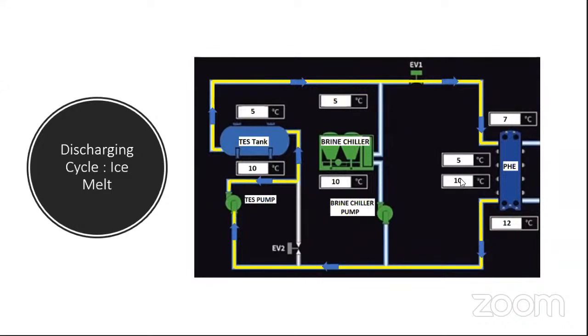Let us start from here. At 10 degrees centigrade, the brine solution is traveling here, and it is being drawn to the thermal storage tank. Across the thermal storage tank, the brine cools down to 5 degrees centigrade. And at 5 degrees centigrade, it comes to the PHE. Now, at 5 degrees centigrade it enters, and at 10 degrees centigrade it comes out. And here the temperature is shown on the water side. Let's say they are 7 degrees centigrade and 12 degrees centigrade.